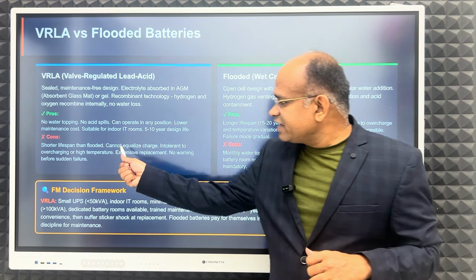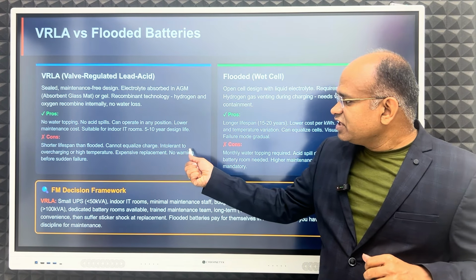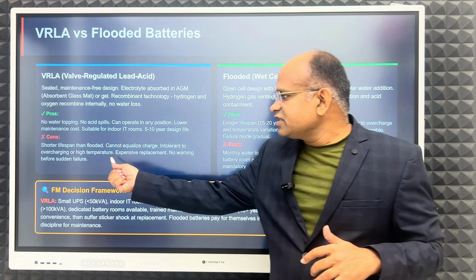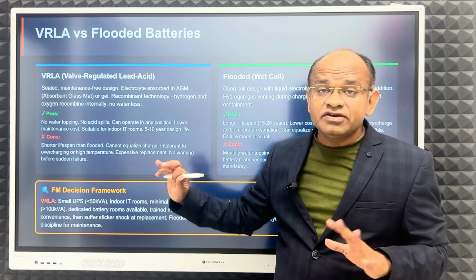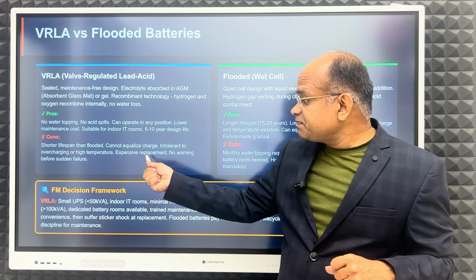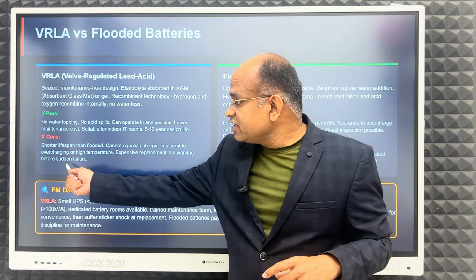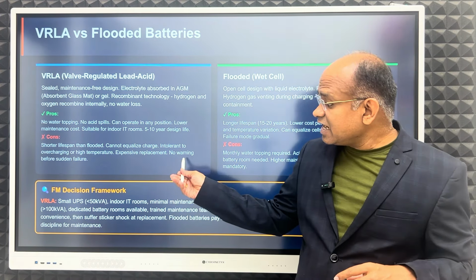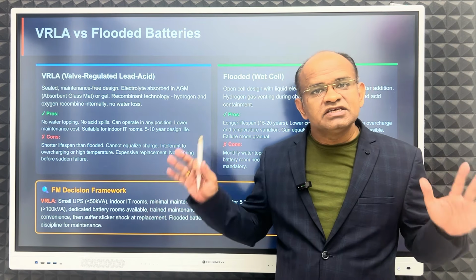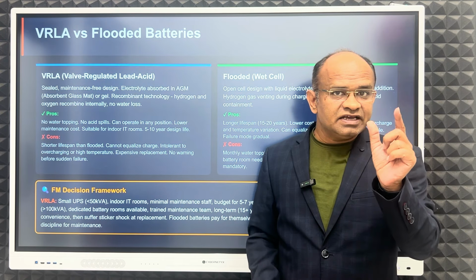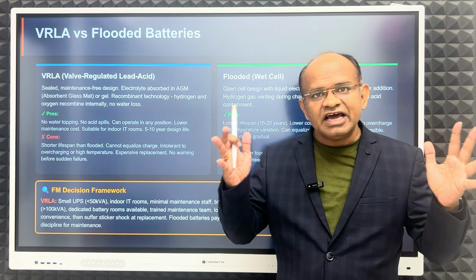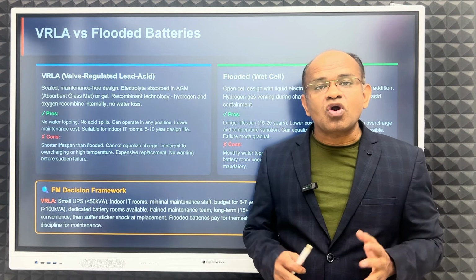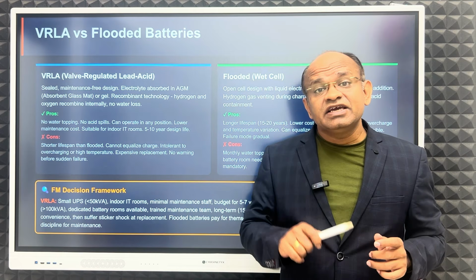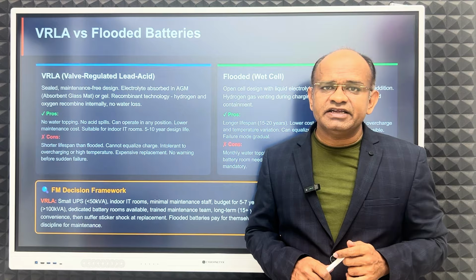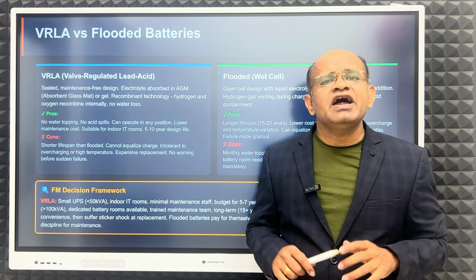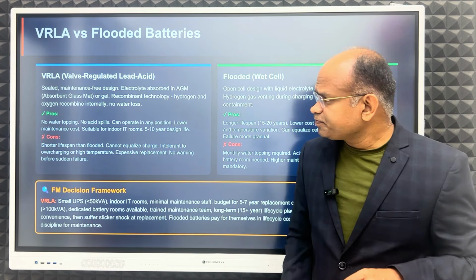With VRLA batteries, you cannot equalize charge, they are intolerant to overcharging or high temperature. Then there's expensive replacement, no warning before sudden failure. Any cell can go wrong and then the entire battery will fail. You need to change that particular battery in the string, otherwise you will not get proper voltage level or power backup.